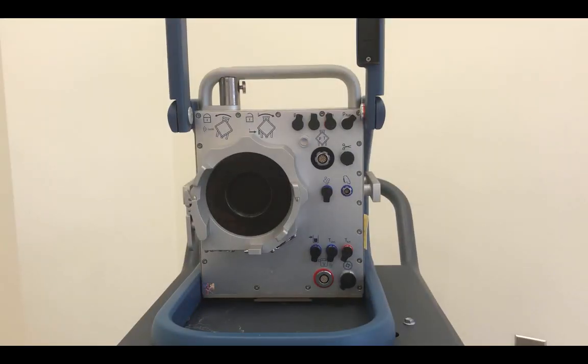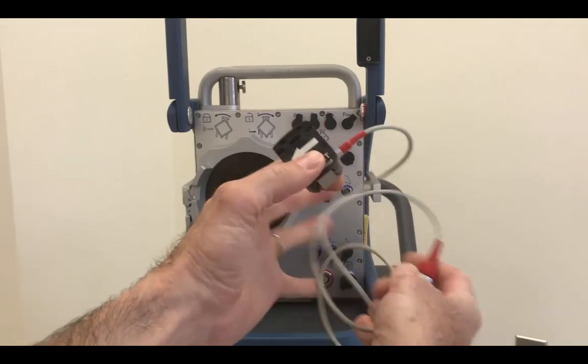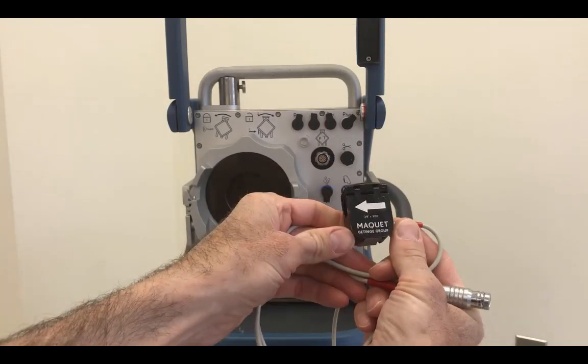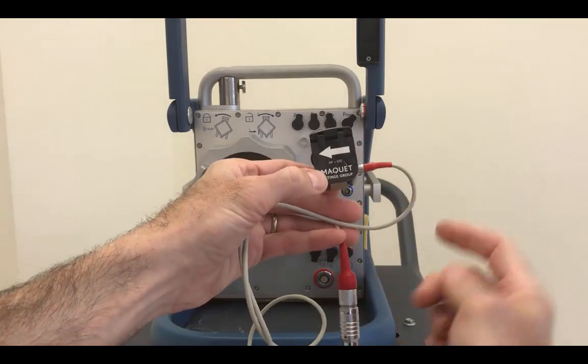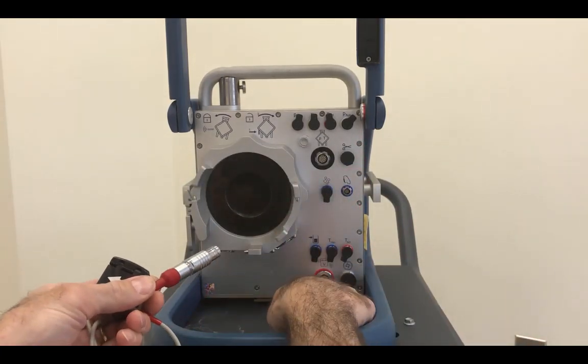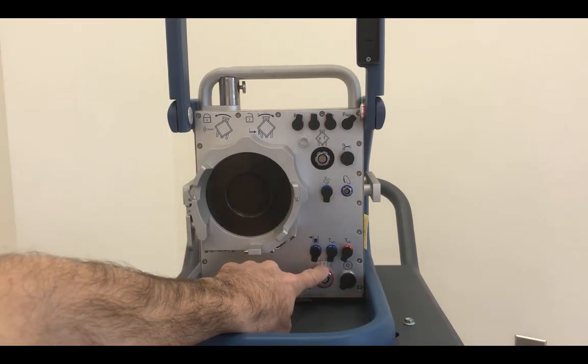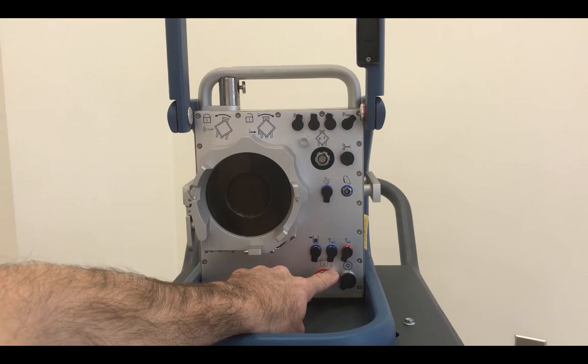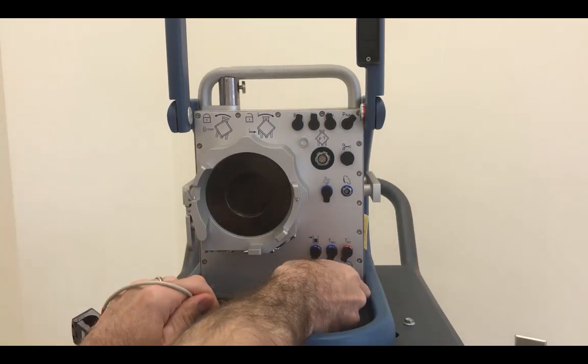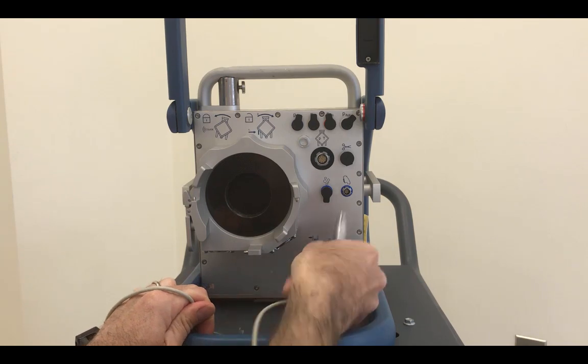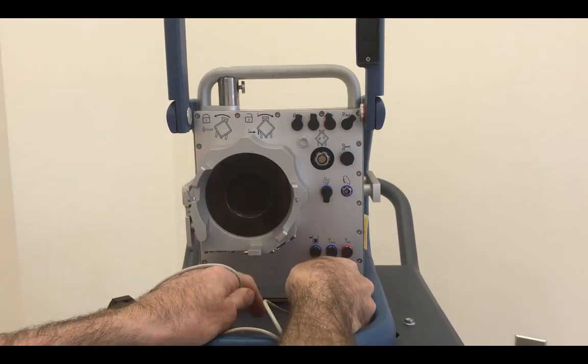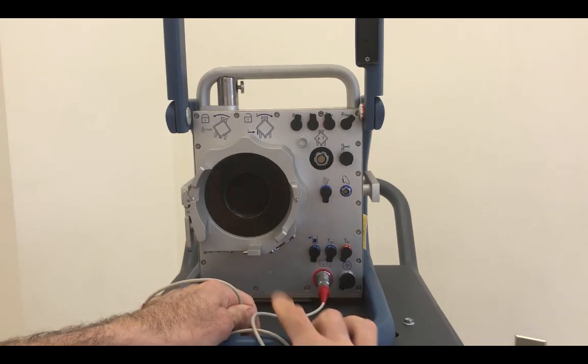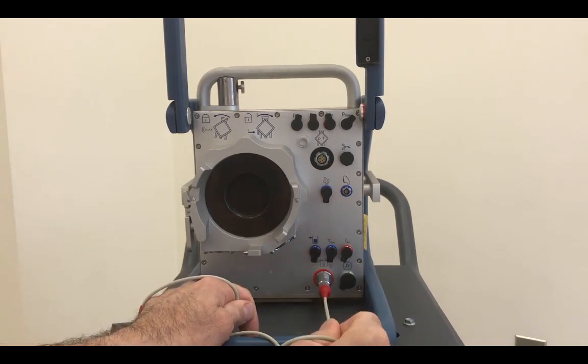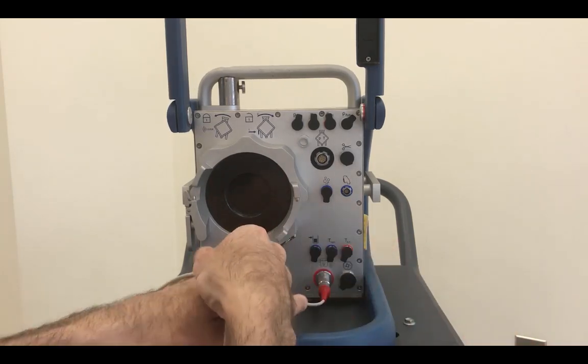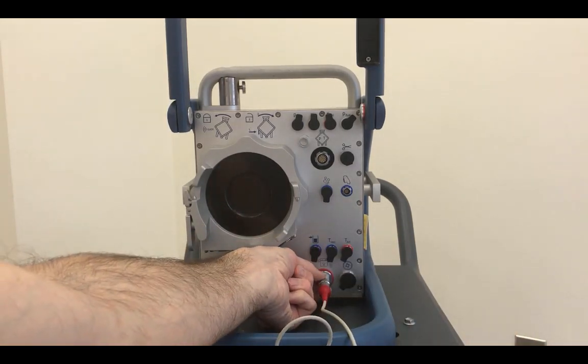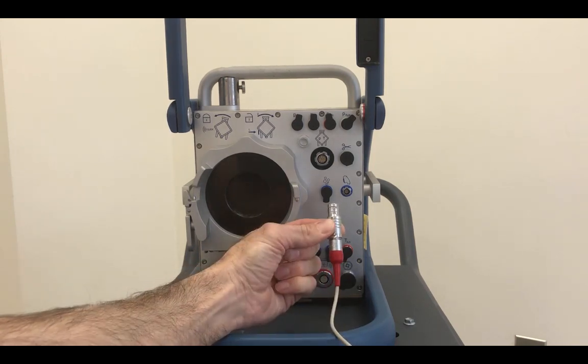If we start at the bottom, this is an arterial flow probe and bubble detector with red markings on it. Corresponds with a red lined port down here, and it shows you a V dot for flow and little pictures of bubbles for the flow and bubble detector, red for the arterial line. Plugs in, red dot, line those up, just push it straight in. And with these connections, now that is secure. To take it off, you grab the collar and pull the collar back towards you, and it comes right out.